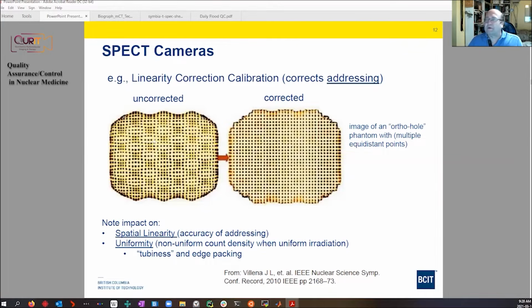That would be the uniformity image. We call that tubiness. I don't know if that's a real word or not, but tubiness. So this results in tubiness because we have these increased count densities correlated with the positions of the PMTs. Also at the edge, for reasons I'm not going to go into, you see that these are closer together. Again, if you squint, it would look like you've got a higher count density at the edge. We call that edge packing.